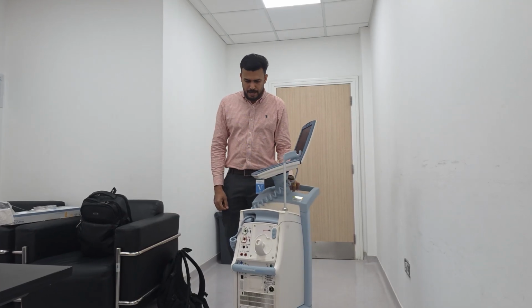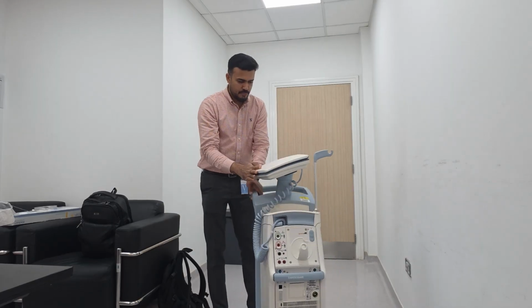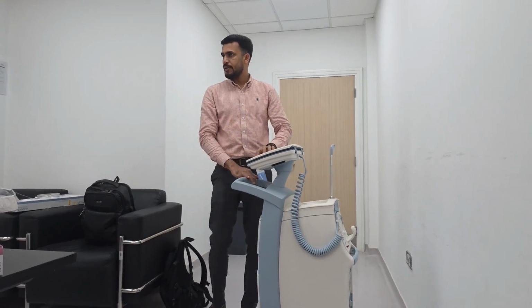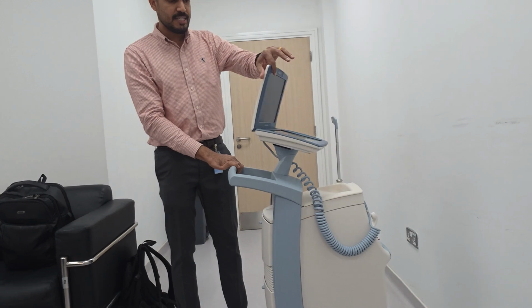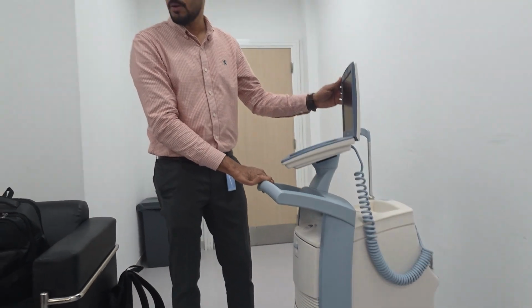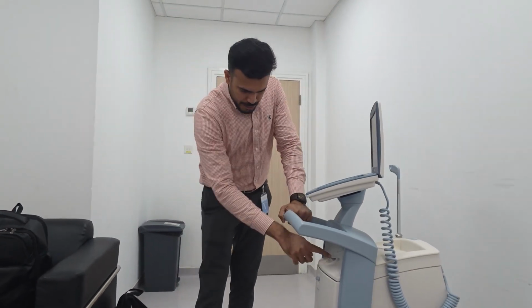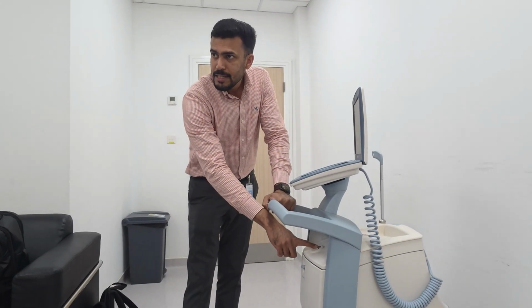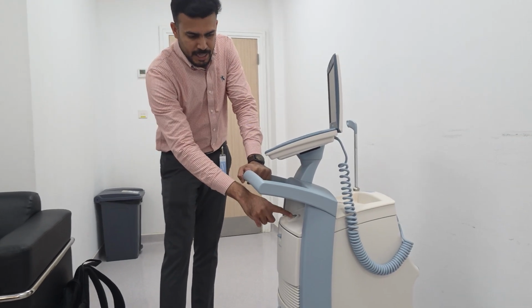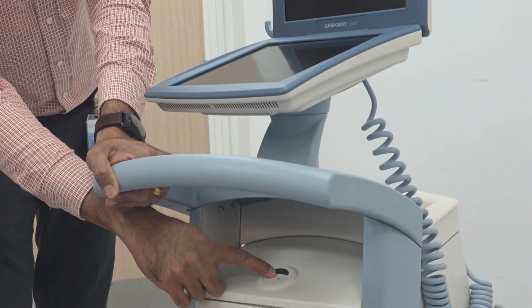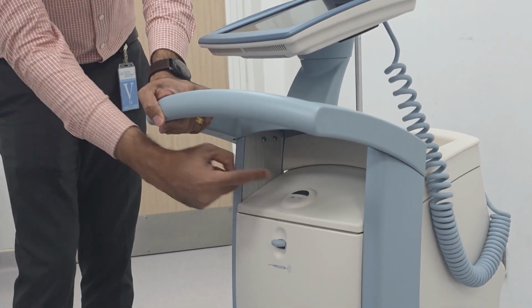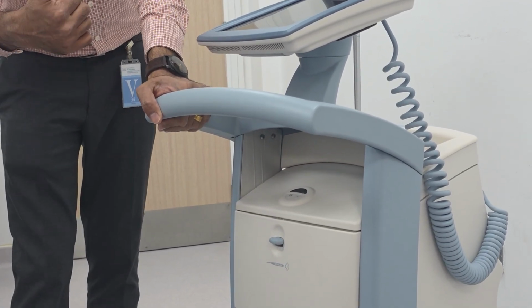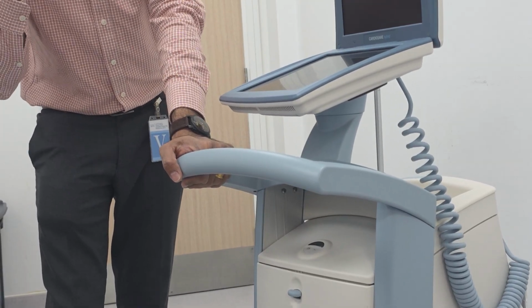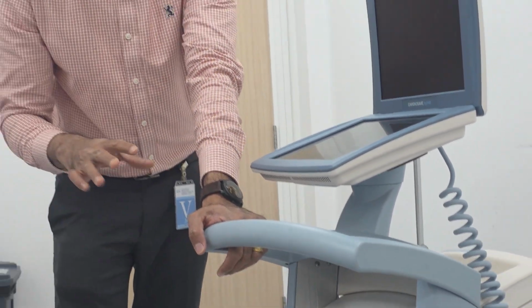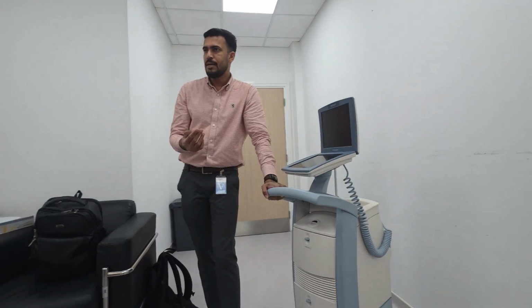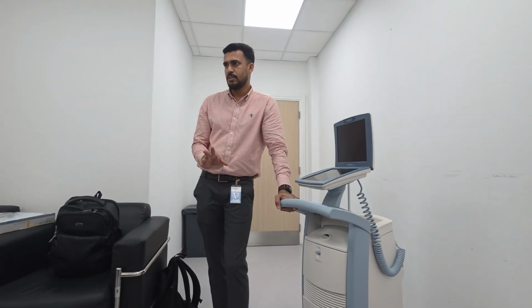Okay, and here this is the front side of the machine where the end users are facing, and the monitor is almost 360 degrees. You can put it in any direction. In the front side you can see the helium gauge. It's an analog gauge. Without switching on the machine, you can see the helium capacity. The green indication is full. Once the needle touches the red zone, it will give you a low helium alarm. So mostly the backup will be around 48 hours, but don't wait for that. When you are getting a low helium alarm, it can work around 48 hours normally.